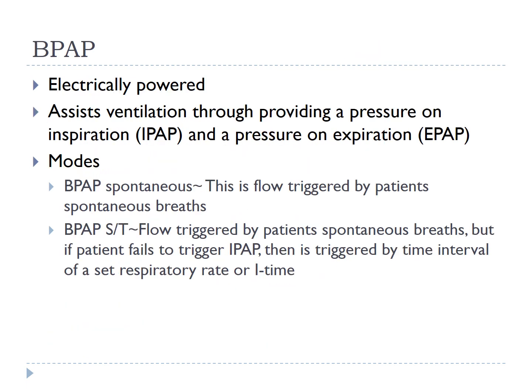Bilevel or BiPAP or BPAP therapy is similar to CPAP. It is electrically powered. It assists ventilation through providing a pressure on inspiration and a pressure on expiration. There are two different modes. You can do spontaneous mode, and this is triggered by the patient's spontaneous breaths to switch from the IPAP pressure to the EPAP pressure. And then there's a BiPAP ST.